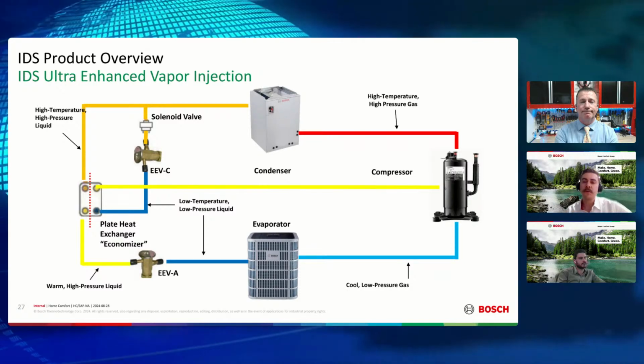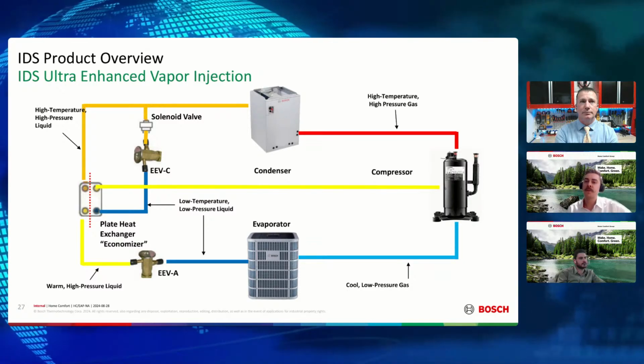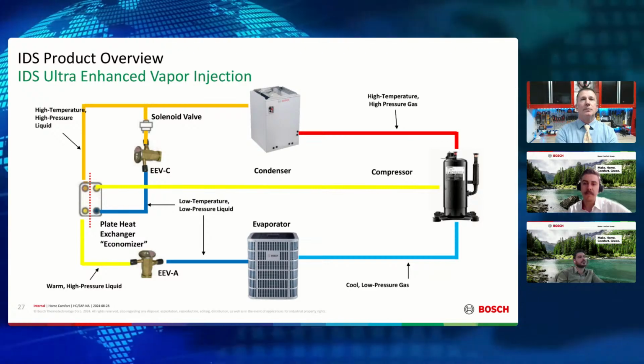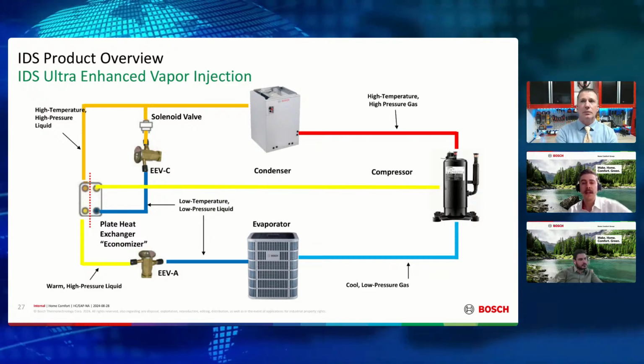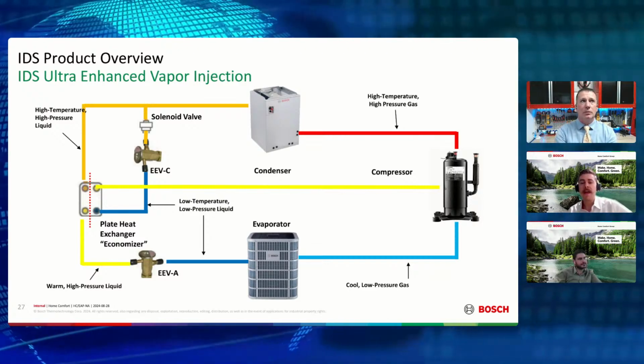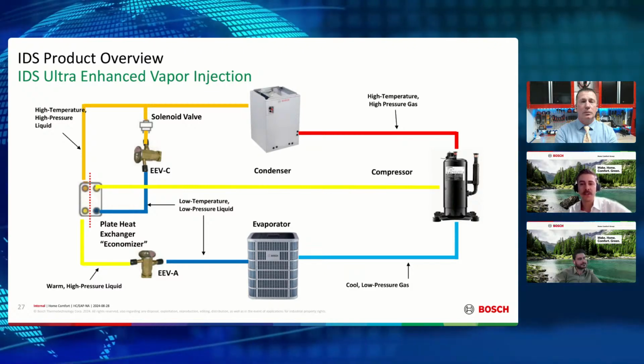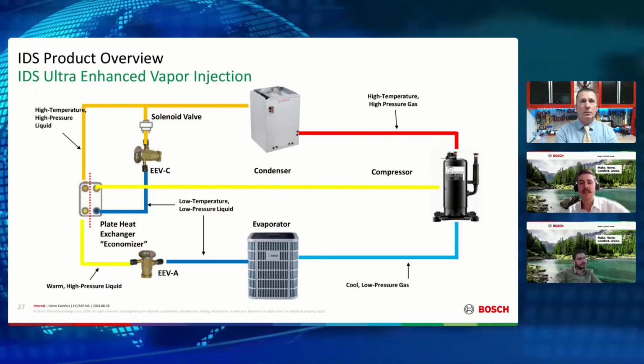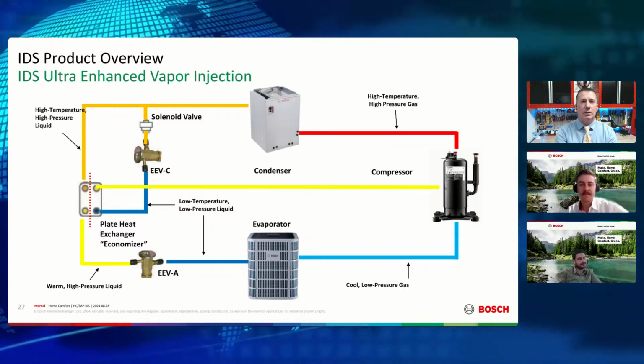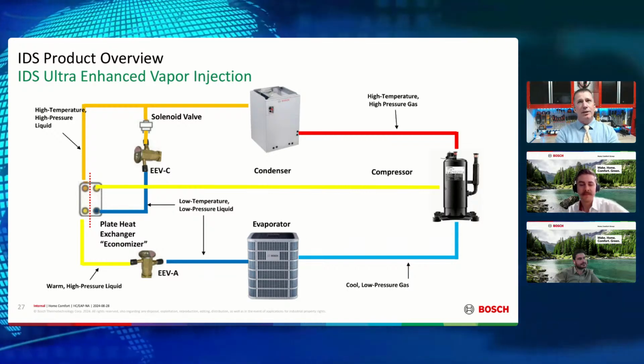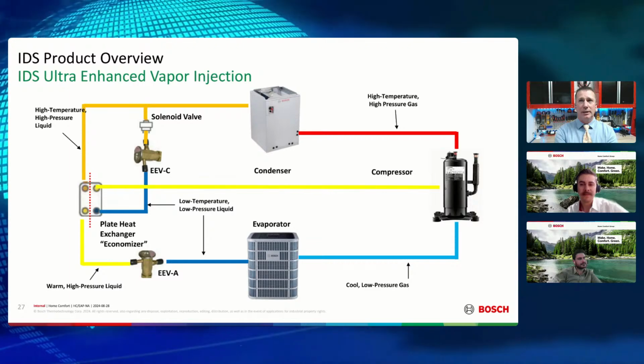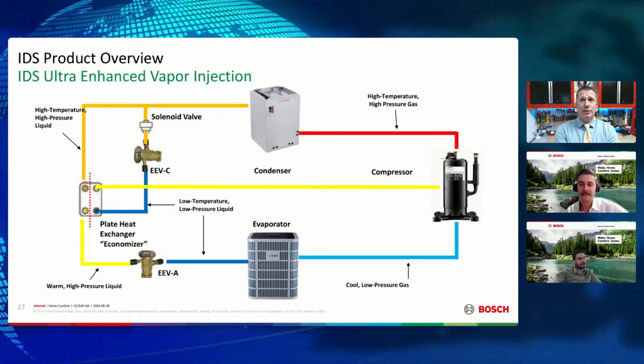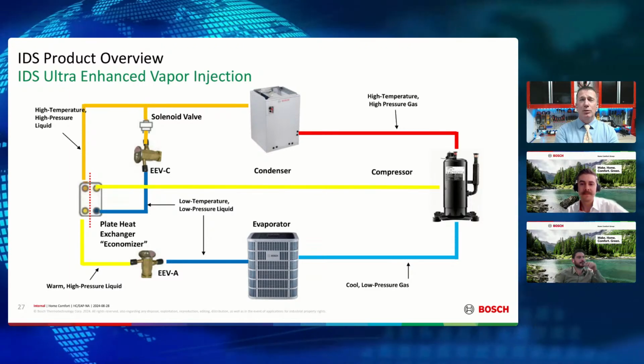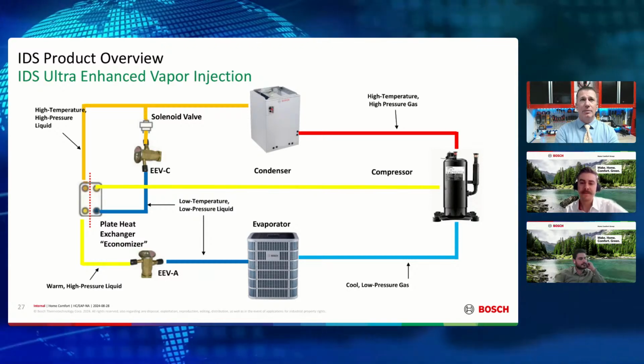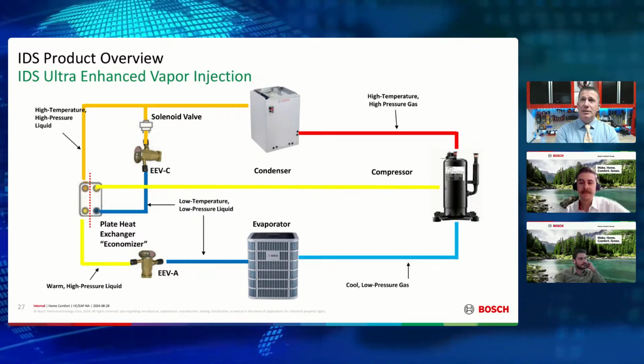Now when we go through our main expansion device, we're further to the left on the PH diagram, meaning our outdoor unit can absorb more heat. That's where we're really buying back that efficiency and increased capacity. So we're just adding a third metering device with our plate heat exchanger—for someone new to this ultra-low-temp environment, it's really not significantly different.